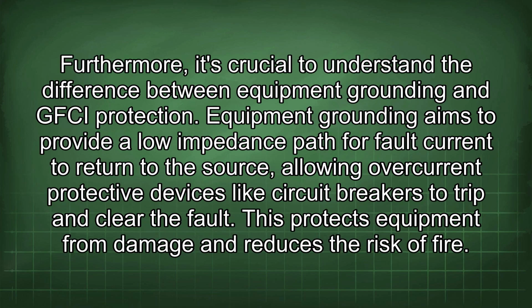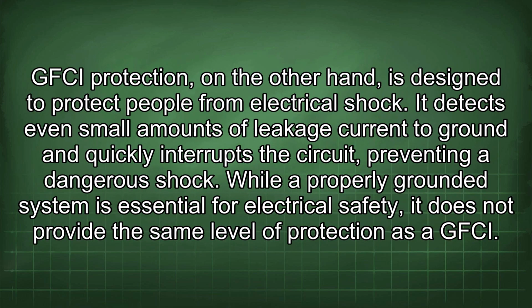Furthermore, it's crucial to understand the difference between equipment grounding and GFCI protection. Equipment grounding aims to provide a low impedance path for fault current to return to the source, allowing overcurrent protective devices like circuit breakers to trip and clear the fault. This protects equipment from damage and reduces the risk of fire. GFCI protection, on the other hand, is designed to protect people from electrical shock. It detects even small amounts of leakage current to ground and quickly interrupts the circuit, preventing a dangerous shock.